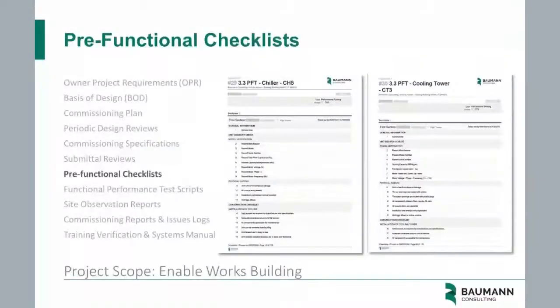For this scope, we provided pre-functional checklists for the MEP systems within scope. These include model verifications, physical condition checks, installation procedures, and method statements for each equipment - chillers, cooling towers, associated pumps, etc. The two photos on the right are examples of a pre-functional checklist created on a commissioning platform for chiller number 5, one of the new chillers, and cooling tower number 3, one of the existing cooling towers.